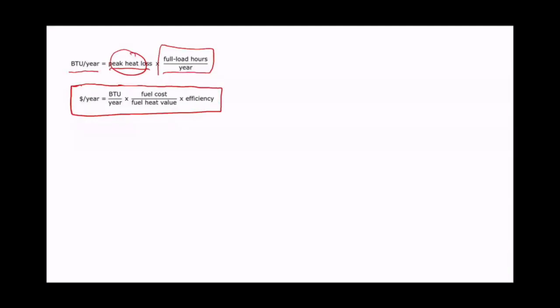So what I just circled is this right here, that BTUs per year is equal to the peak heat loss times the full load hours per year, and that is given on the references formula sheet for HVAC. And that dollars per year is equal to BTUs per year times fuel cost divided by fuel heat value times efficiency. And so what we're doing is we're going to convert our peak heat loss and our full load hours per year into some amount of money it's going to take for us to heat our building. So that's what we're trying to figure out.